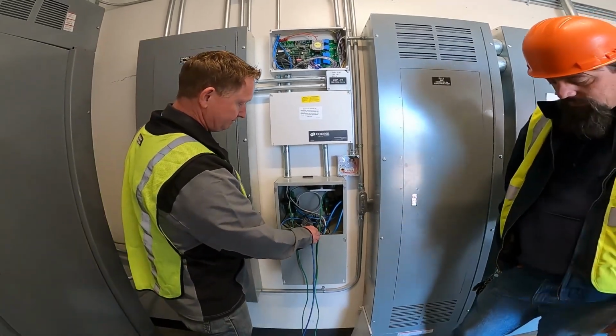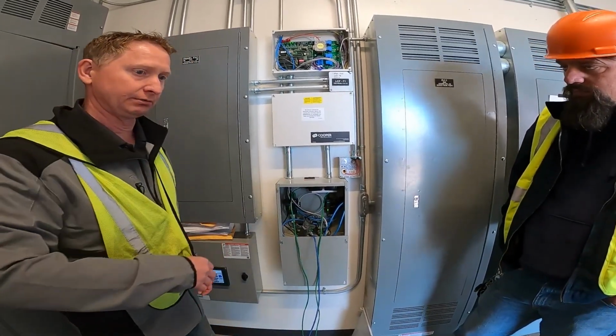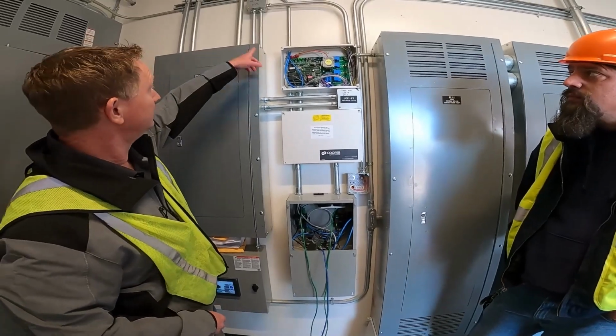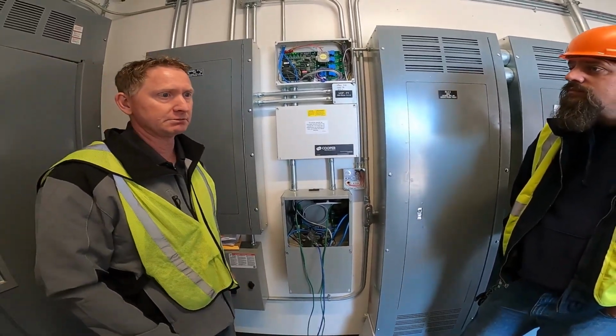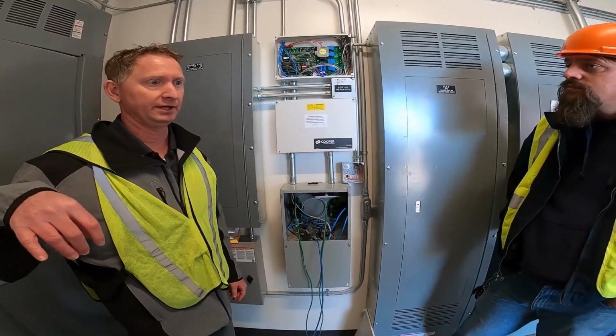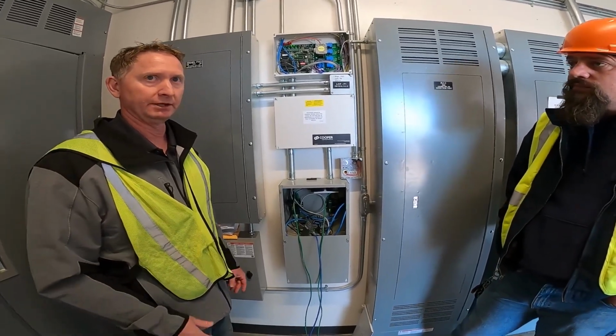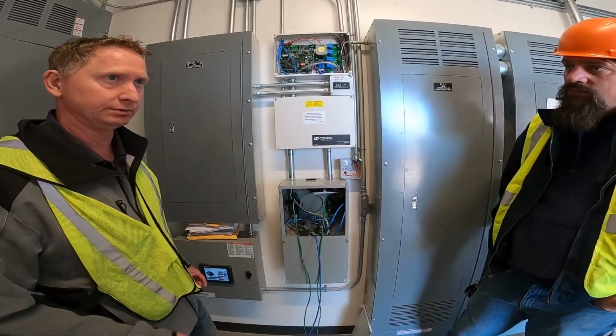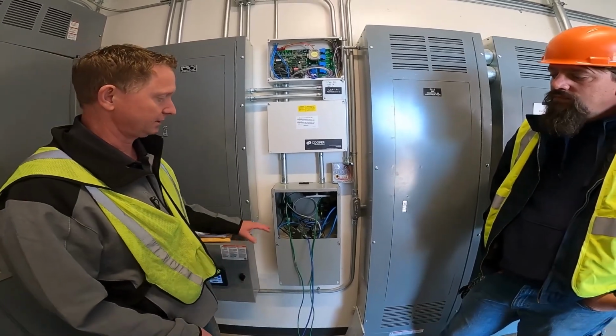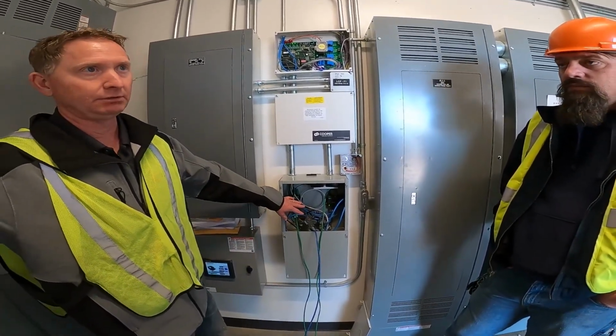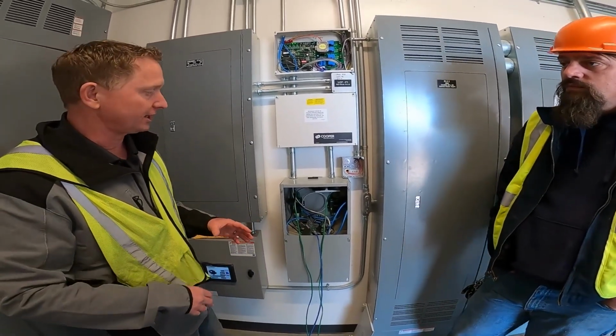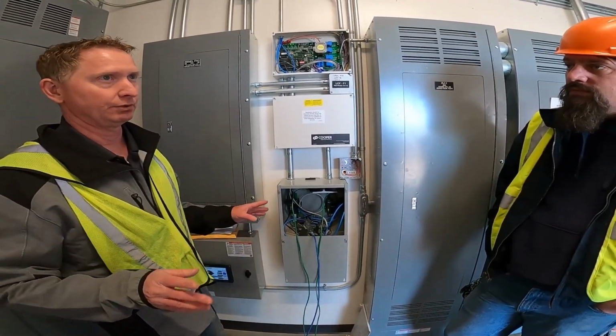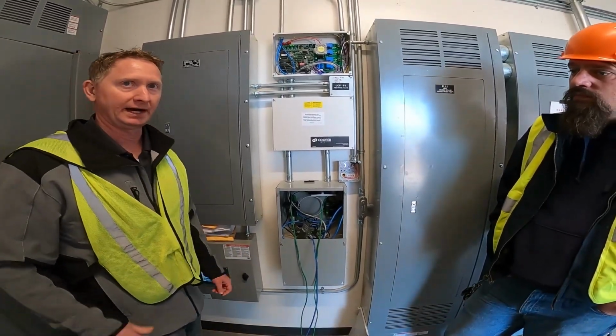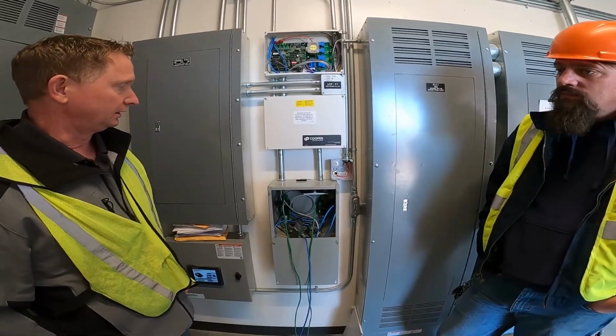These need to be set up on the building network. There's cables ran that go to your IDF rooms, but nothing's programmed or set up yet - no patch cables, no ports enabled or set up or anything like that. So I have it set up as a little mini local network right here so I can do my programming. Once I leave, it's not going to work until your IT is set up in there.